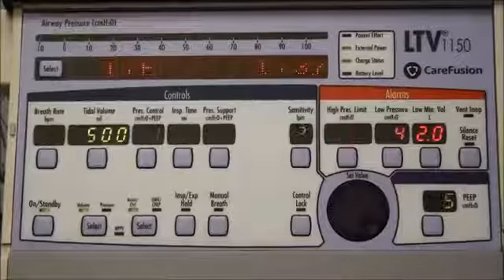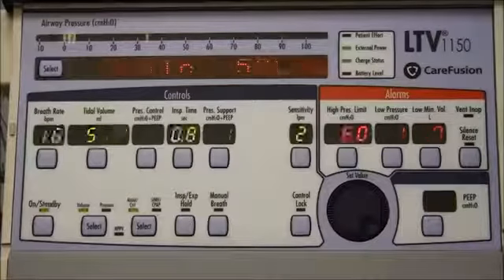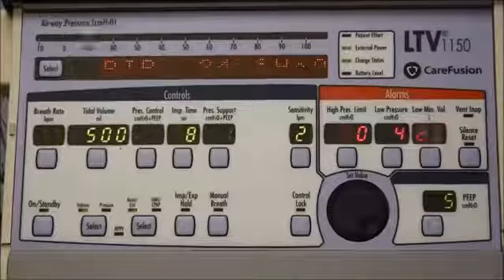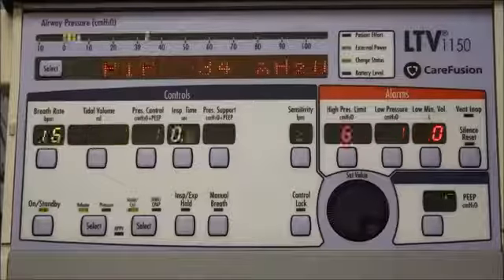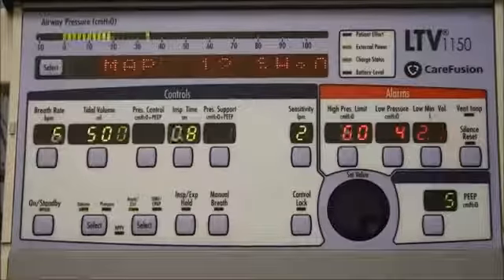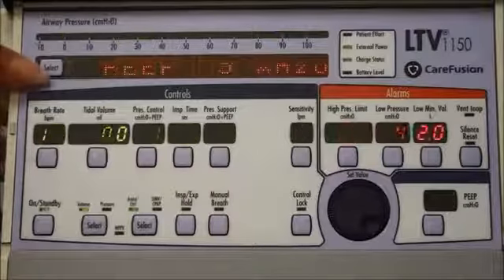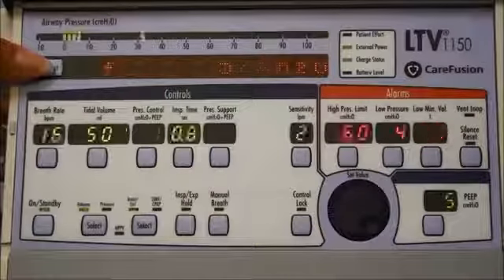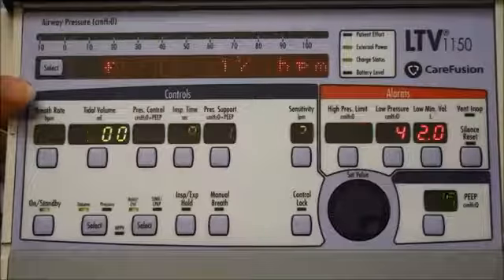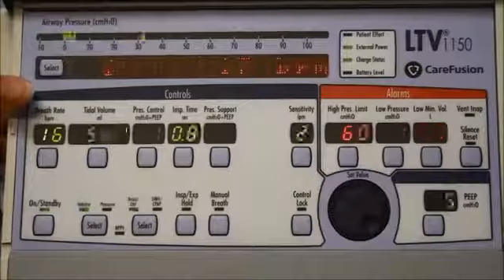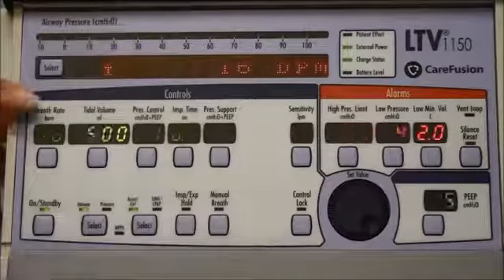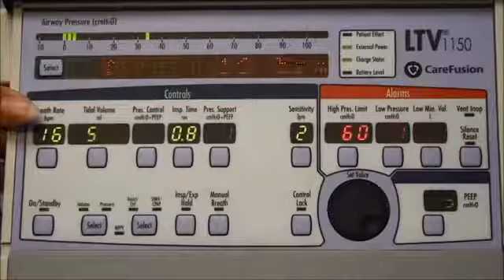Those are some readings that you may be interested in looking at when you're doing your vent checks, and may have to write down on your vent check sheet depending on what your protocol is. If you want to stop it on any particular setting, all you need to do is push this select button, and it'll stop on a setting. Right now it's showing us the breath rate or frequency.